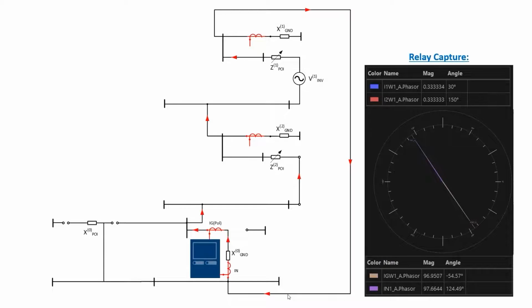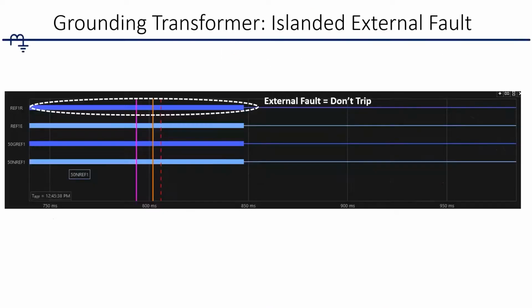So the interesting thing with this is, if you go and draw out the symmetrical components aspect of it, it's the same thing. It's being injected into the polarity side, and then it goes into the non-polarity side. But notice that the magnitudes are almost nearly the same this time. So you don't have any contribution from the grid. It's simply from the grounding transformer at this point.